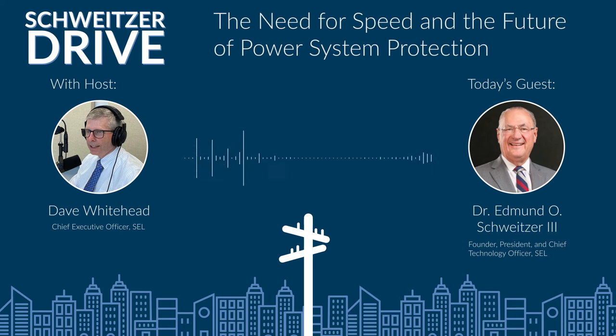That's really interesting. Thinking about the fault as we traditionally think about it, something happens on the power system and we start pushing a bunch of current into that fault. These are large magnitude fault events. But if we turn it around and now we have a traveling wave relay, we're detecting it so fast. And if the breakers were quick enough to open up, you'd no longer be interrupting fault current. Rather, you'd just be breaking load current, if we could do it in a handful of milliseconds. It's really amazing to think about.